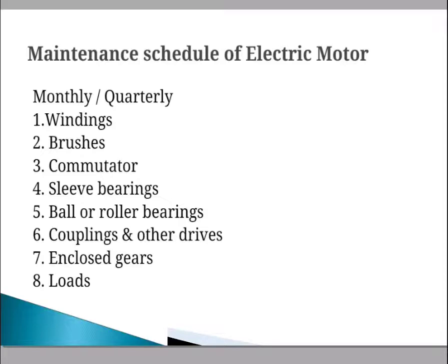Then brushes: we have to check the brushes for proper fitting and free play in the brush holders. Brush spring pressure should be noted, and you have to check whether the brush pressure is proper or not. Worn out brushes should be replaced, because they play a more important role between the winding and commutator.